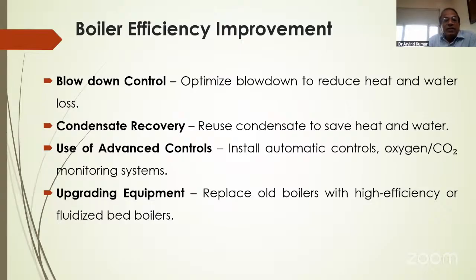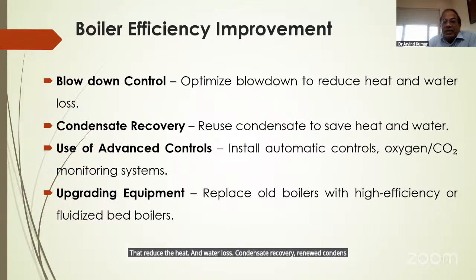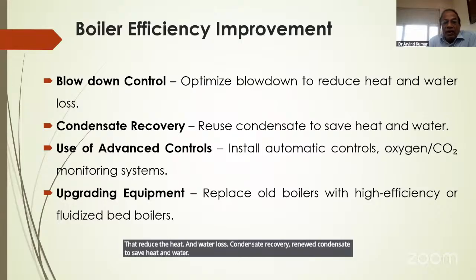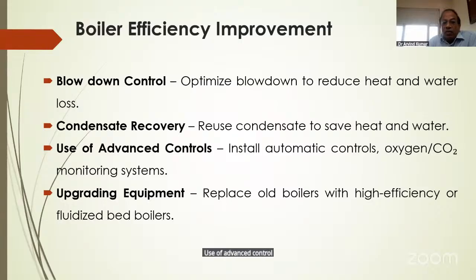A lot of energy is wasted in the blowdown, so blowdown control should be optimized to reduce heat and water loss. Condensate recovery: reuse condensate to save heat and water. Use of advanced control: install automatic control and oxygen and CO2 monitoring systems. Upgrading equipment: replace old boilers with high efficiency or fluidized bed boilers.